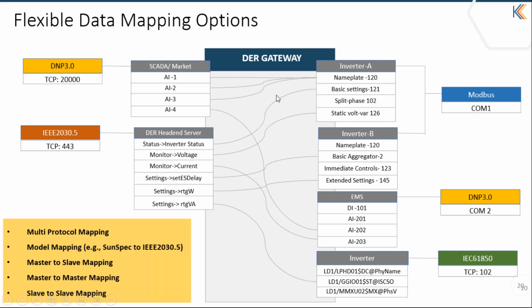And in addition to that, the framework also provides flexibility for master to master mapping. This is primarily used for getting data from the field through a master protocol like Modbus, getting inverter data from Modbus and sending it to an RTU over DNP3. You can do a master to master mapping here, and inverter data can be directly sent as a command to the RTU. Similarly, slave to slave mapping is also supported. Like if you have SCADA systems on DNP3 and a DER deployment, SCADA needs to send out commands to the system. You have a slave to slave mapping, and the commands from DNP3 will be redirected within the gateway to the DER system. So that's the flexible mapping option.